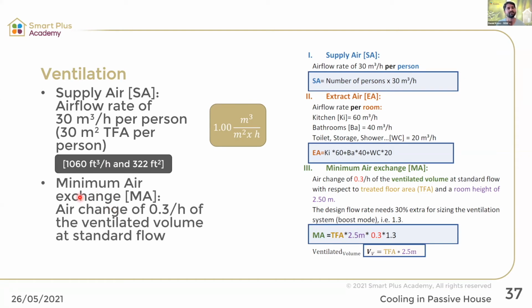And then, so this is from the supply air minimum, the minimum air supply that we have to have. We have to have at least an air exchange from inside to outside of 0.3 by Passive House teaching, and that comes then to 0.7 cubic meters of air exchange. Here, this is from our formula sheet where it explains exactly the whole limitation. I'm leaving out the extract air rooms because they're really individual and they're normally not the dominant one in that calculation, but could be. Good.